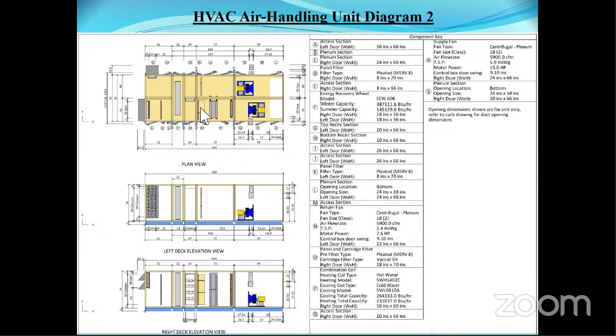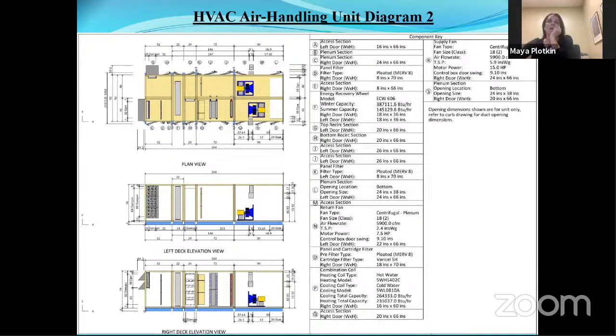The reason for that is we would have to have MERV 13, or let's say MERV 14, there anyway. So it would be a matter of upgrading that to MERV 16 rather than just adding it at K. If we did a MERV 16 there, we'd have a very big pressure increase because we'd still have to have it at O. That was discussed a little bit last week, so it would just be an upgrade from 14 to 16.